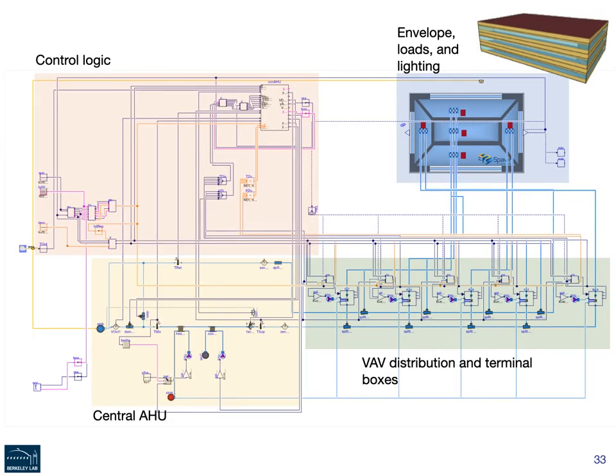In a larger setup, such a system model may look like this: on the top left is an implementation of the control logic, the yellow indicates a central air handler unit, in green is a VAV distribution system with terminal boxes, and in blue is a multi-zone building and envelope model that uses Spawn of EnergyPlus, coupled to EnergyPlus during runtime.